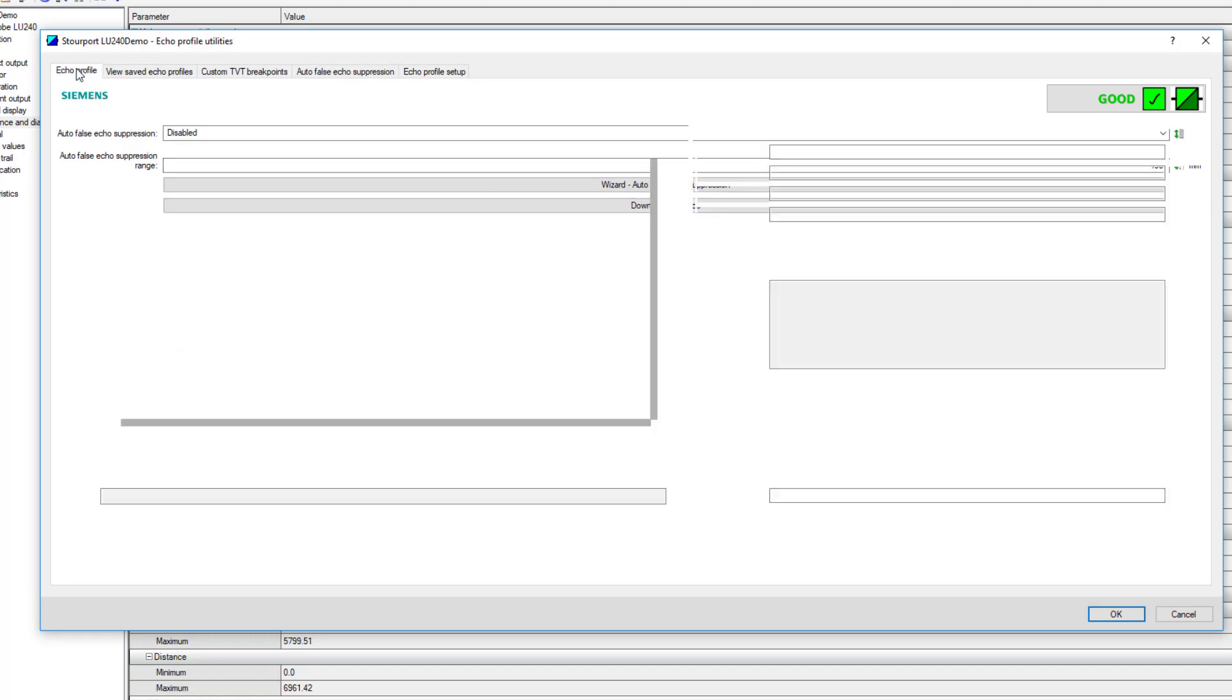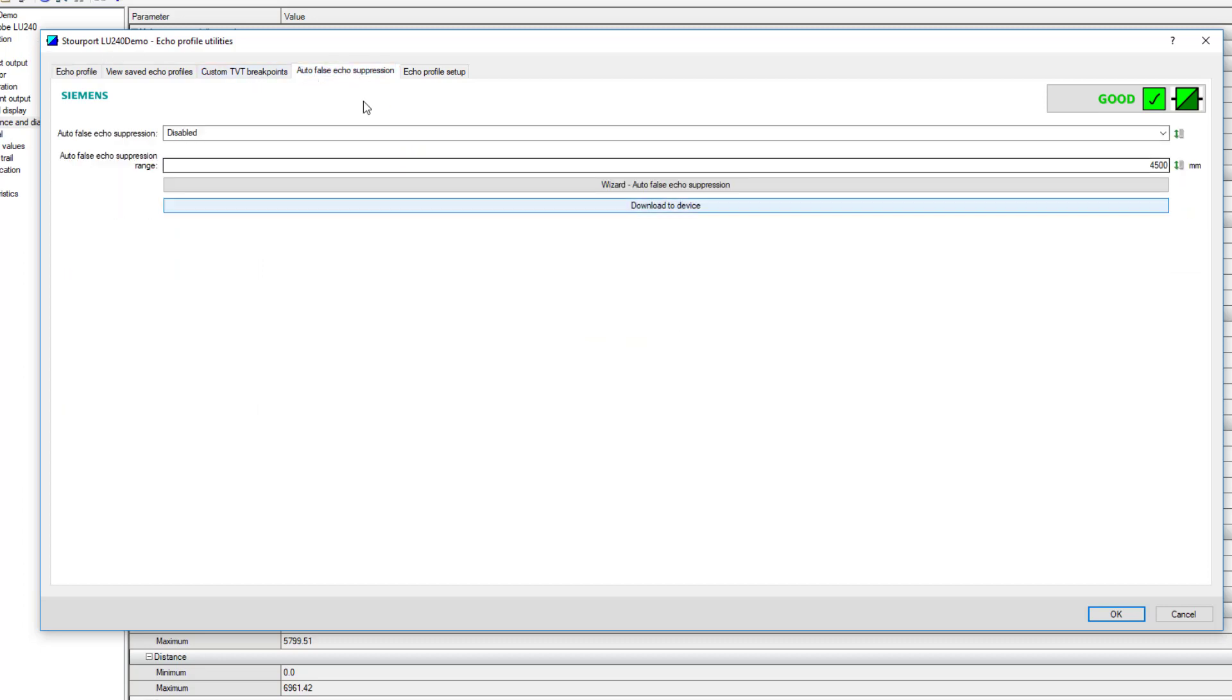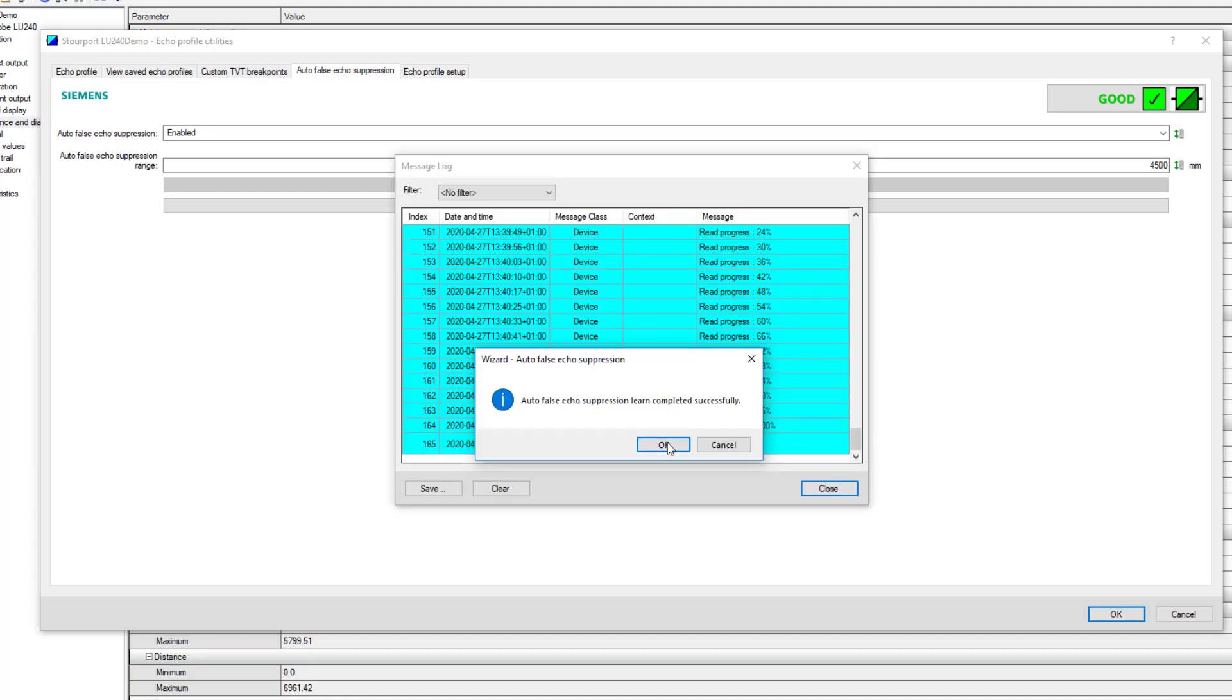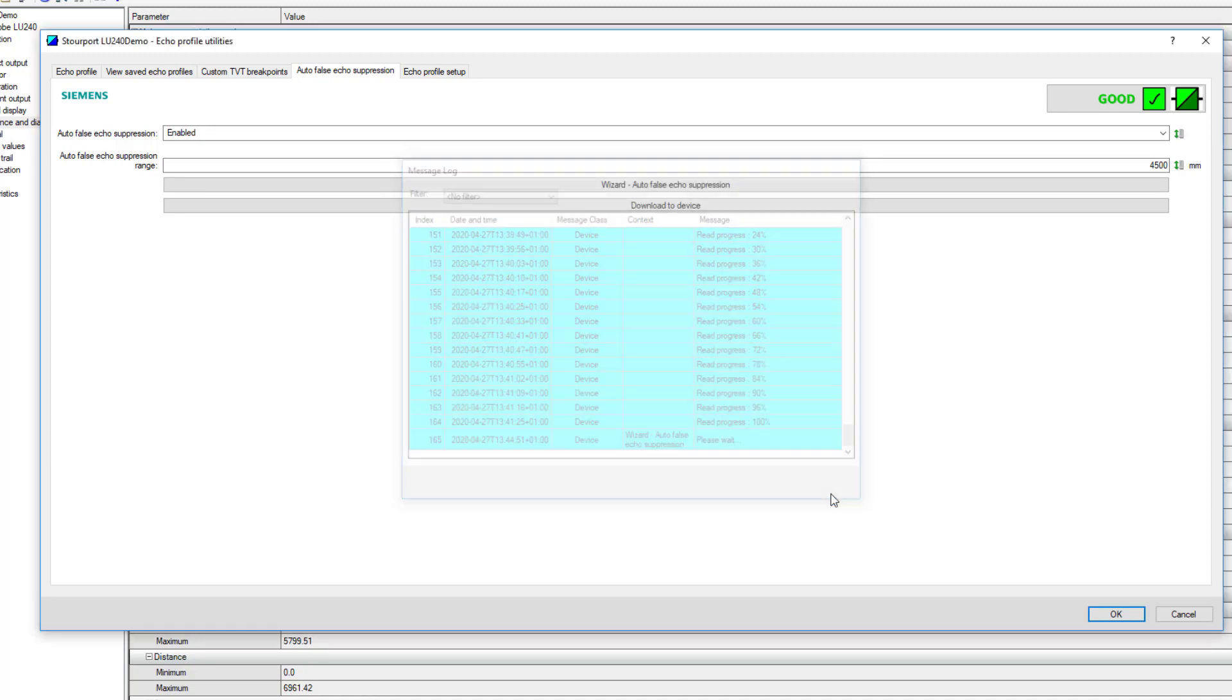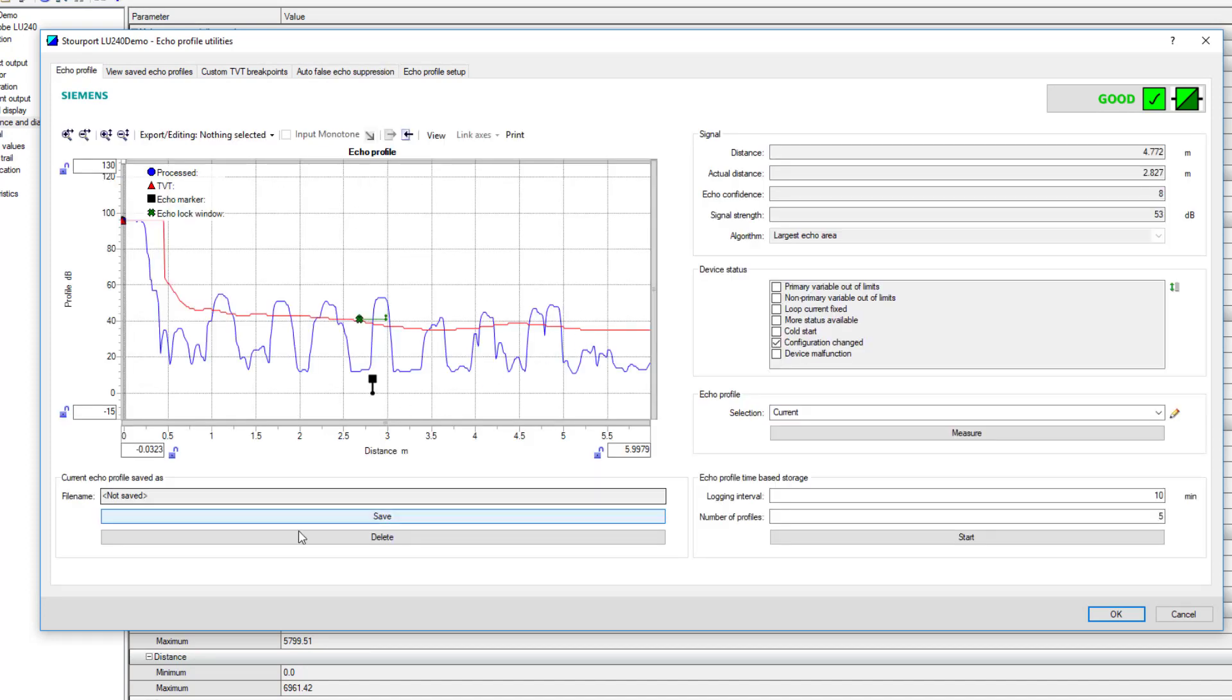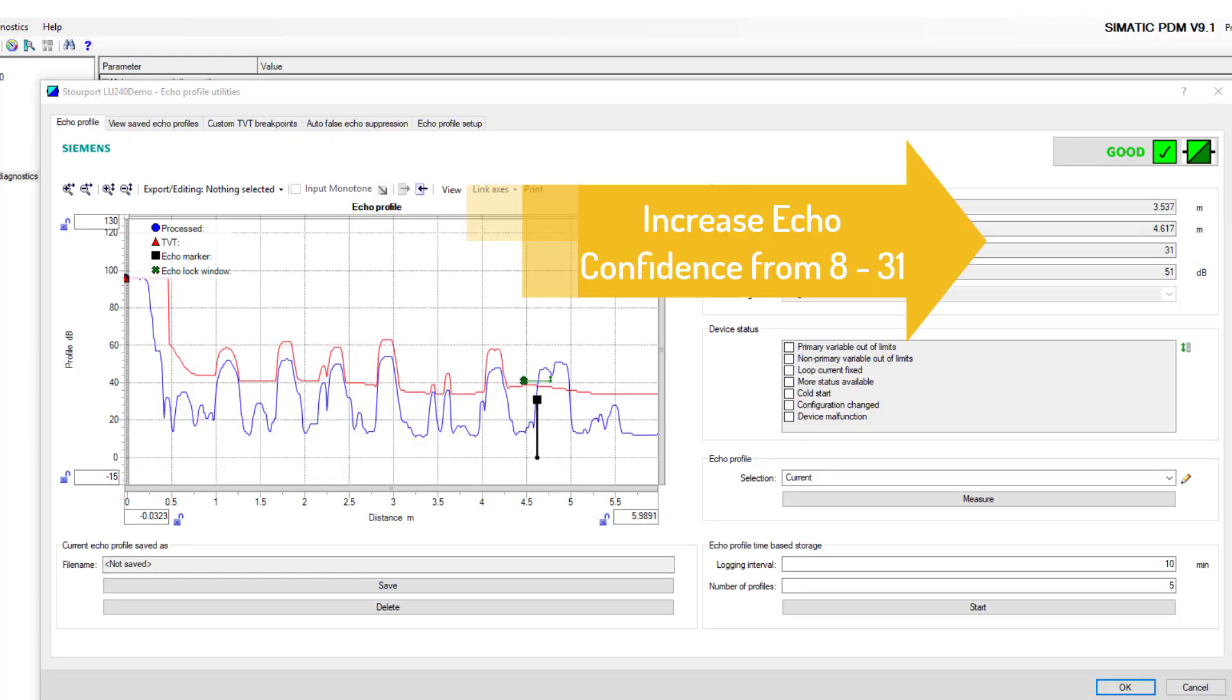If we go back to our device, our true level starts at 4.5 meters. If we go to the auto false echo suppression wizard and set our level, everything before 4.5 meters we're classing as false echoes and fixed obstructions. That procedure is now complete. All we have to do is take a new measurement.